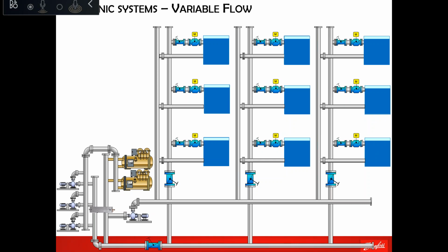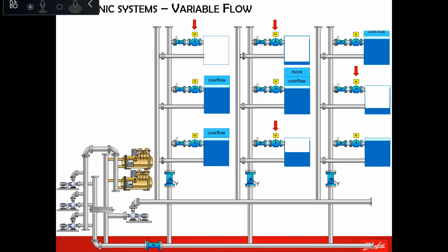After the manual balancing part is done, modulation of the control valve will start. And since 99 or even let's say 95% of the year, we are running our systems in part load condition, we will never be able to have peak load condition except in that 1 month during the daytime. So the control valve will be permanently closing and opening to achieve the comfort level required by the area. Now, if the control valve is opening, again, we are back to the same first scenario, which is overflow and underflow.